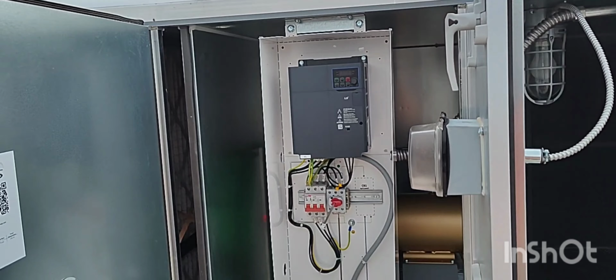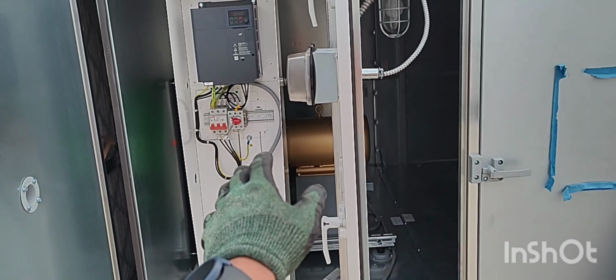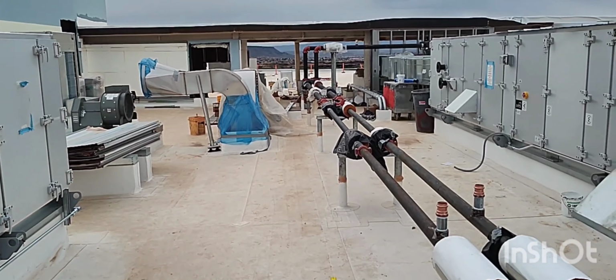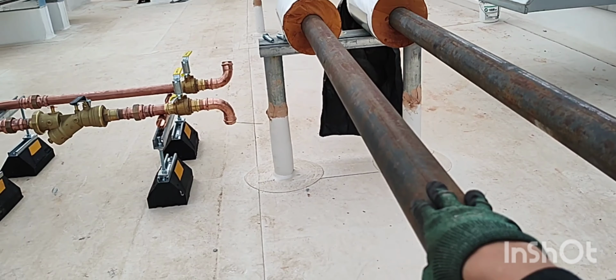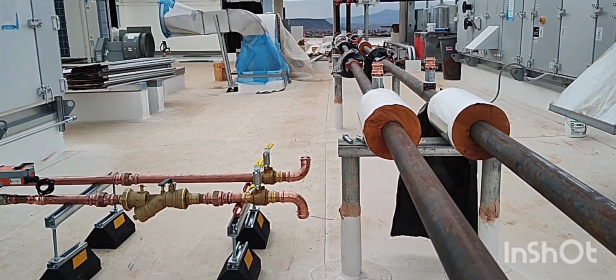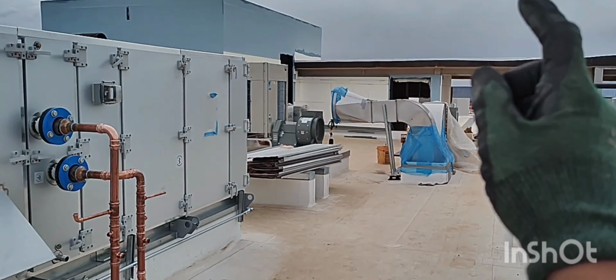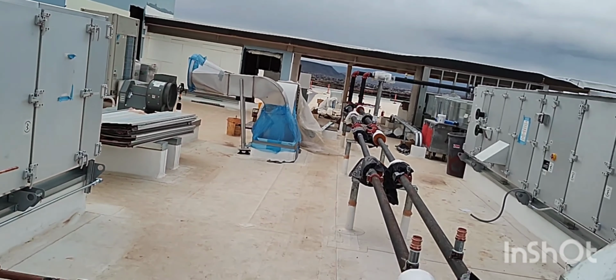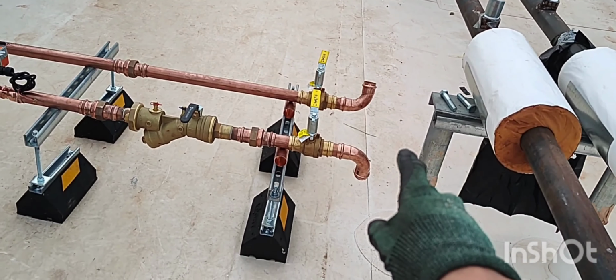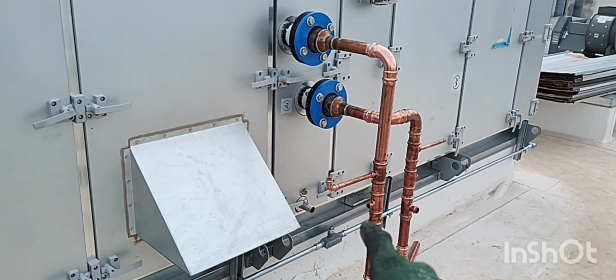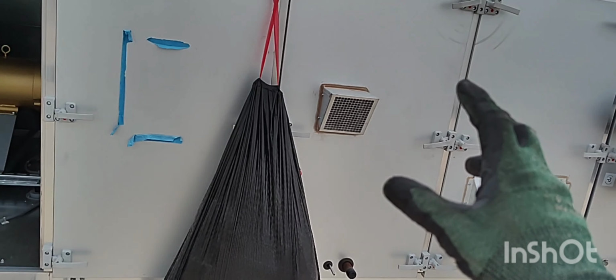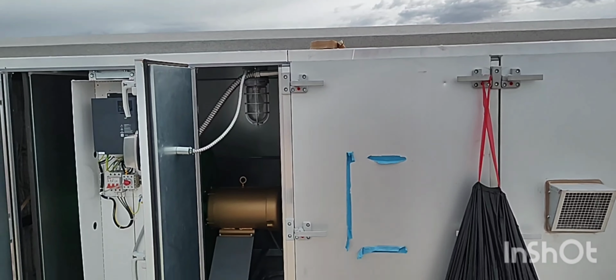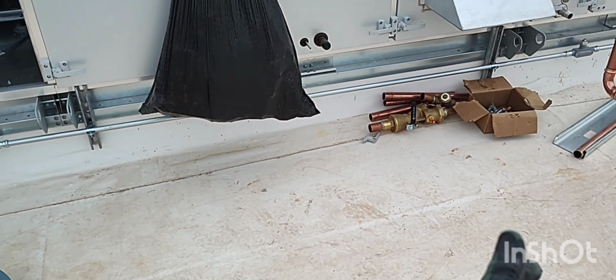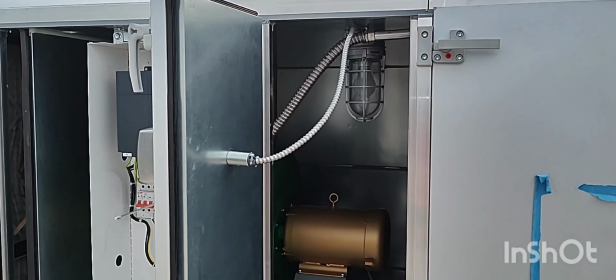We're here on the roof again, and essentially what we're doing today is we're going to size the conductors going into this motor. So how this system works is these plumbing parts right here, these lines coming in, they're going clear across the job site to the cooling towers. That sends cool water through these, and it's going to cool down the air. And then what is going to blow this air throughout the whole entire building? This motor right here.